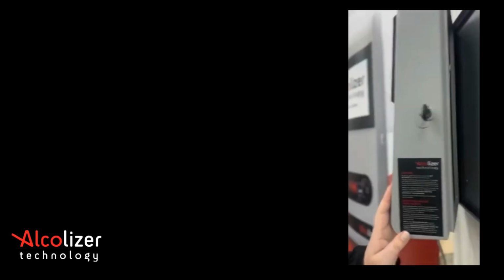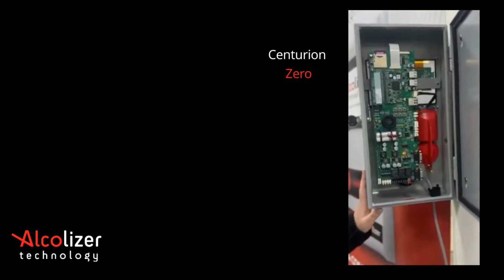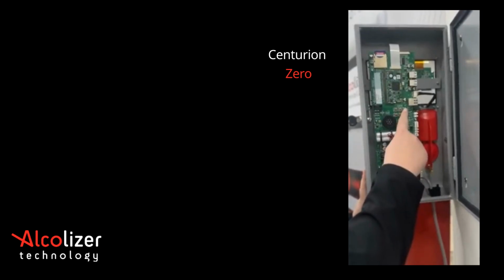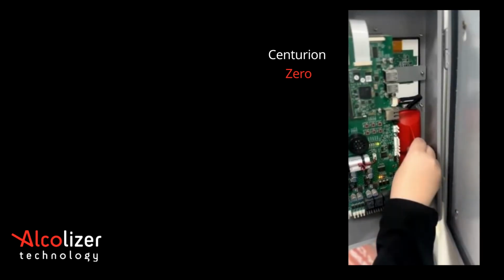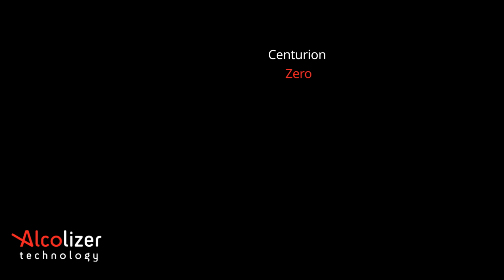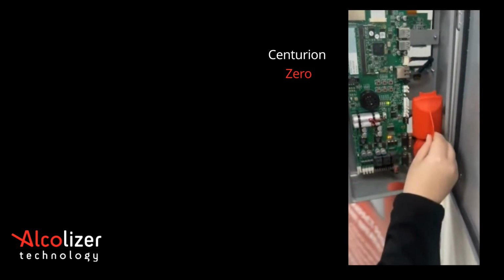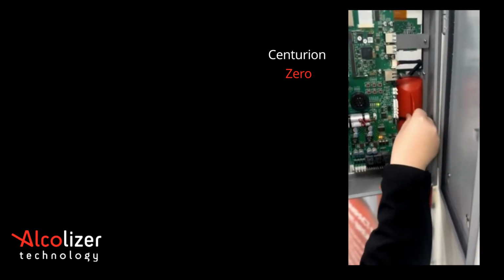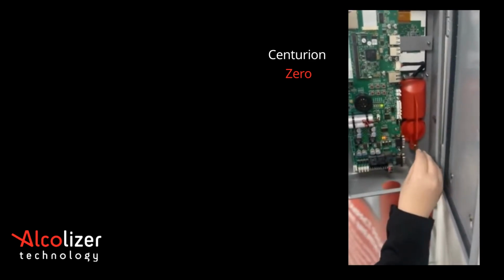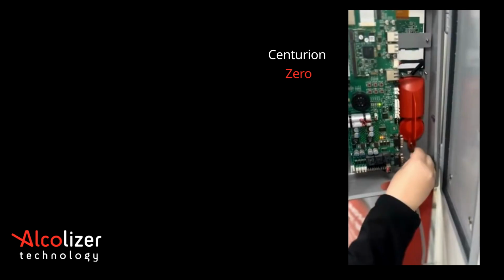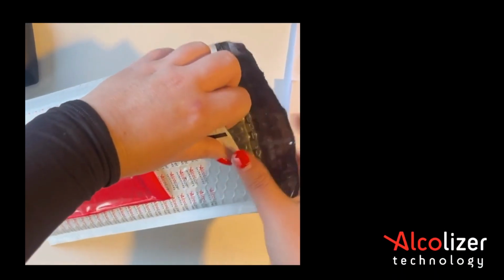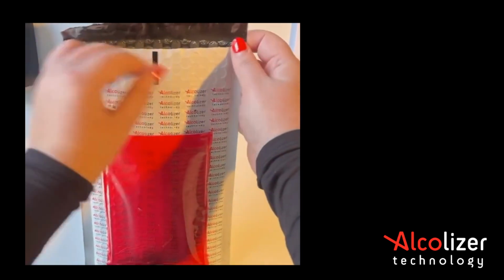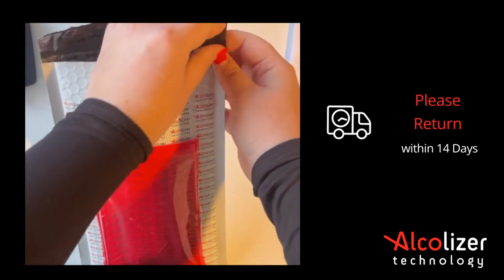For Centurion Zero, open the device and press the off button. Remove the expired module by unscrewing the aluminium thumb nut and carefully removing. Insert the new calibrated module and tighten the aluminium thumb nut to secure. Press the off button again to restart the device and close the unit. Please return all expired modules in their original packaging with the return label attached within 14 days to avoid replacement fees. Your calibration is now complete.